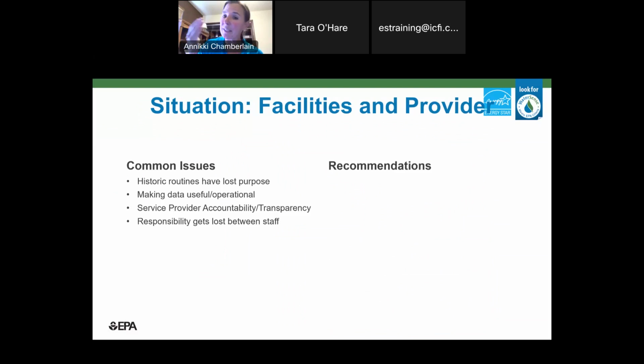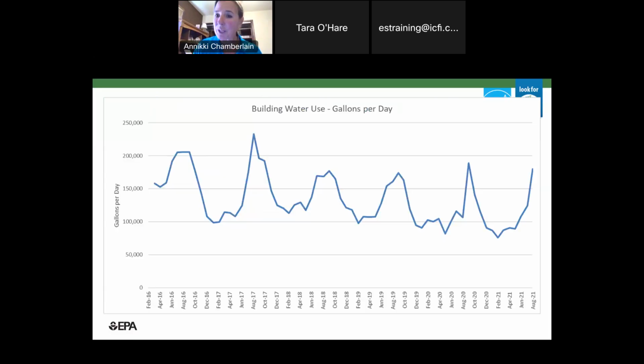A lot of times what we see, this is hospitals, banks, we see good routines that maybe have lost their meaning over time. And the service provider, people are just like, I'm sure they're doing good, a little bit lack of accountability. So here's a good example. This was a property that, this is their building water use, does not include irrigation. So I can see these big summer spikes. So I know that that's cooling. They have a big, beautiful cooling tower. So we're looking at approximately 100,000 gallons of water use a day. So that's quite a bit.